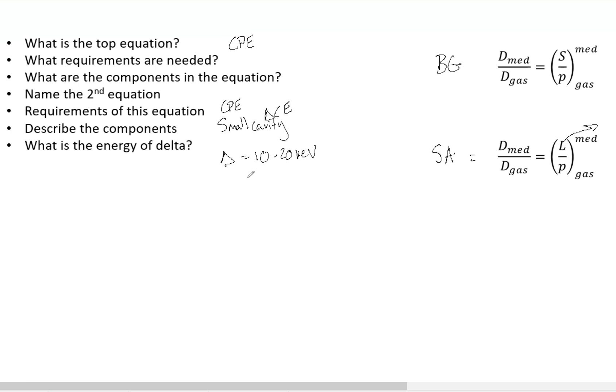So that is why Spencer-Attix is what we use. It only requires a small cavity, and it doesn't have that unrealistic expectation that Bragg-Gray theory has. So understand Bragg-Gray theory and Spencer-Attix, why it's important.